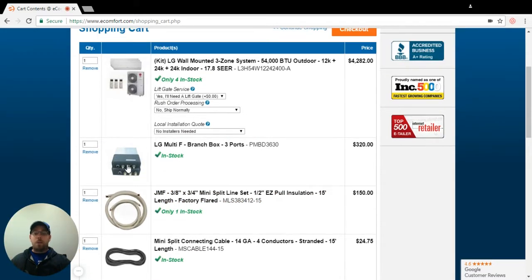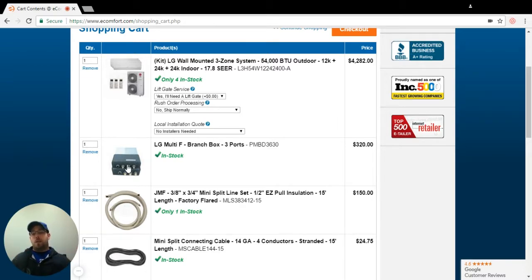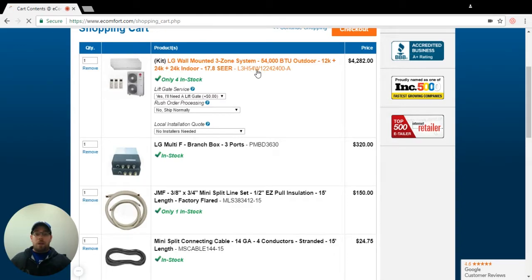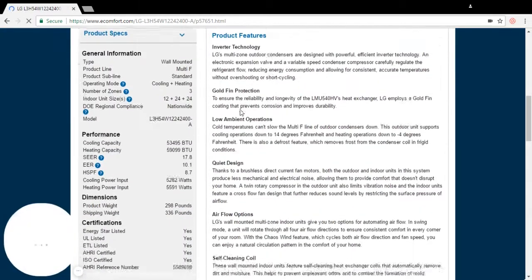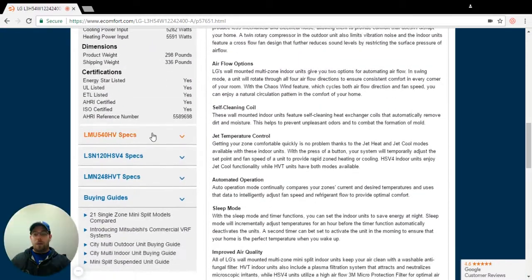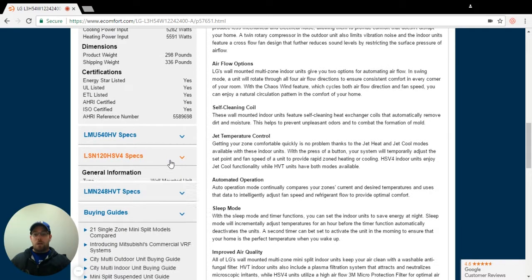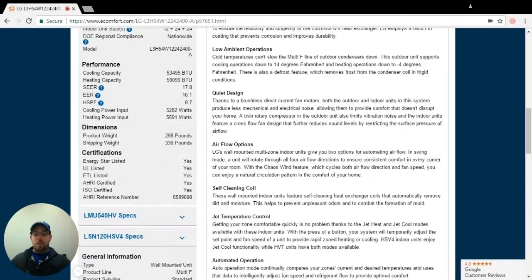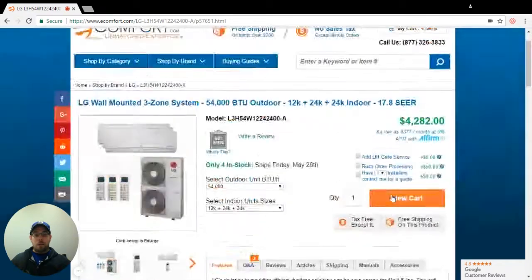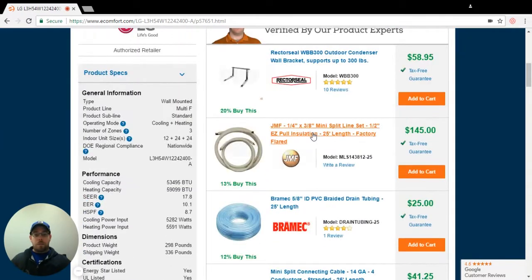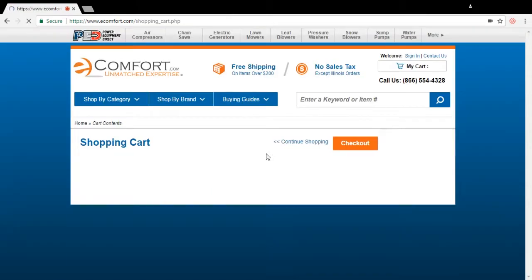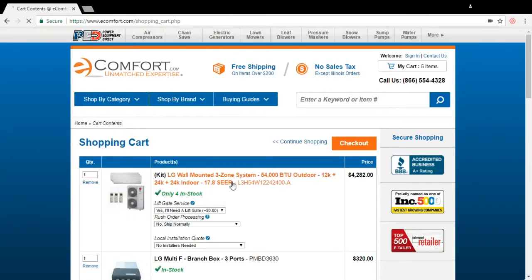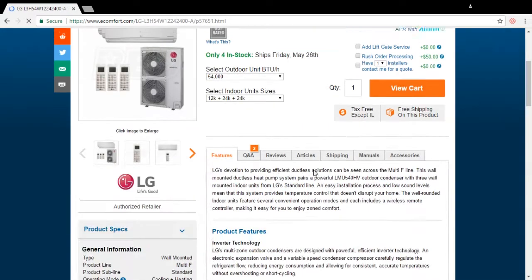Now I need to know the distance between my branch box and each individual indoor unit. So I'm going to say, in this case, my 12 is going to be about 25 feet away. So what size line set do I need? Quarter by three eighths. So here's a quarter by three eighths. Now I need 25 feet. Added that to the cart.